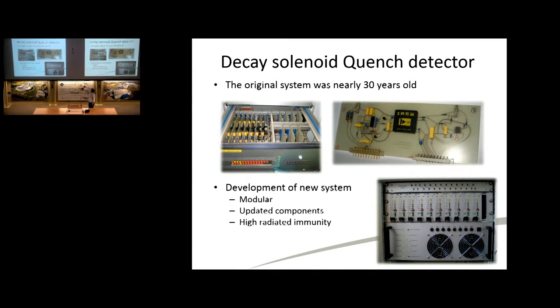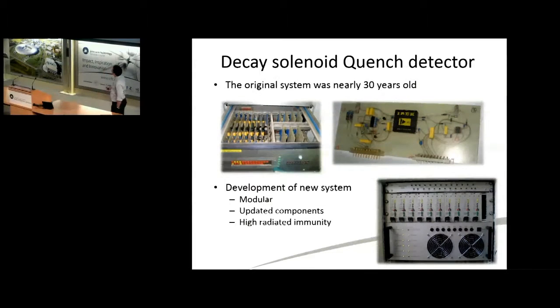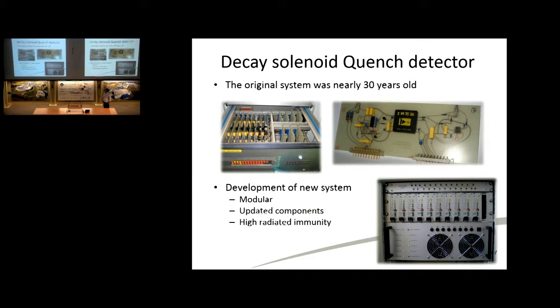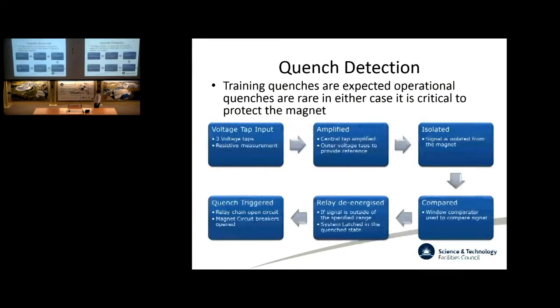But we were worried about the integrity of the system, so I developed a modular system here, which has worked successfully for the last probably 3 or 4 years now. I updated all the components, new isolation amplifiers, all new amplifier circuits, much more modern manufacturing techniques. I wrapped it up in this nice EMC crate, which isn't very EMC in that picture because there's a big gaping hole there, but we filled that in, and we managed to get a very reliable, very robust system. The power supply and interface unit is down here that handles all of the communications between us and the quench detector, the control system and the quench detector. So we like this system.